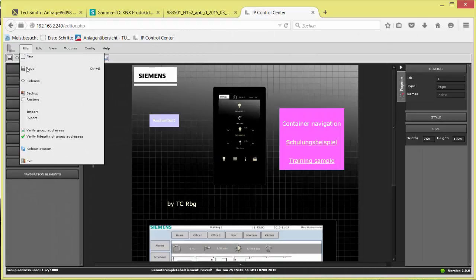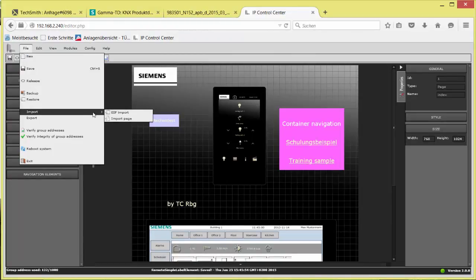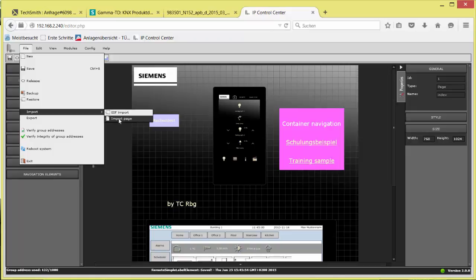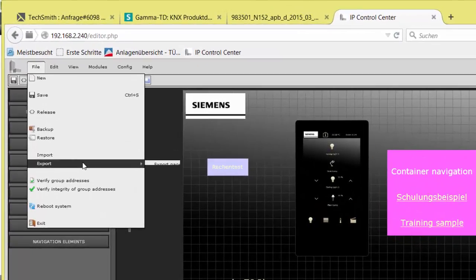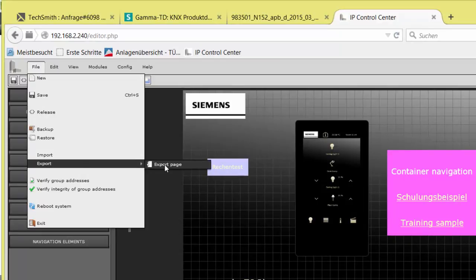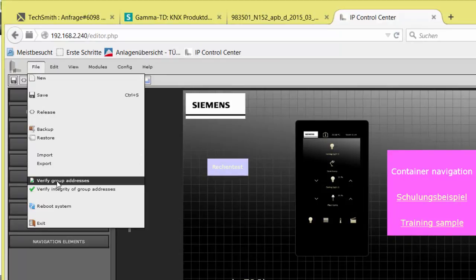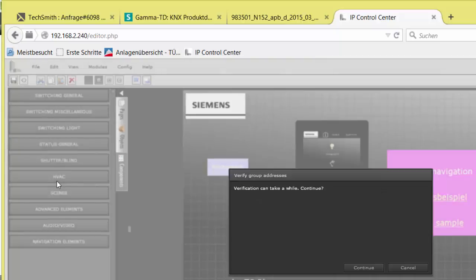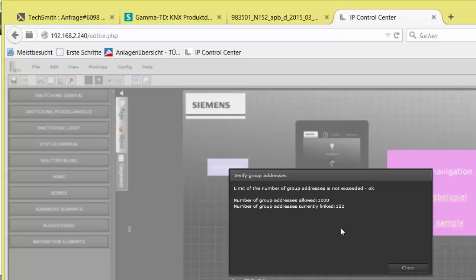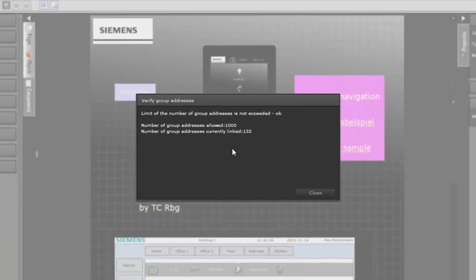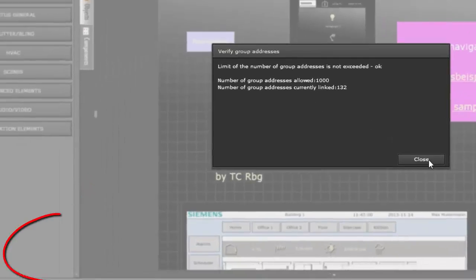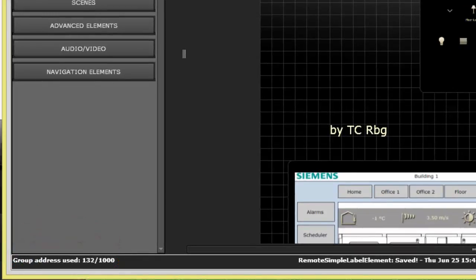Existing description texts and data point type subtypes can be optionally replaced by the ESF Import. A single page with all components but without address or object links can be imported as well as exported. Verify group addresses shows the present number of already used group addresses from the maximum 1000 via OPC or ESF. This status info is also shown in the status line left corner. The number increases only after saving.